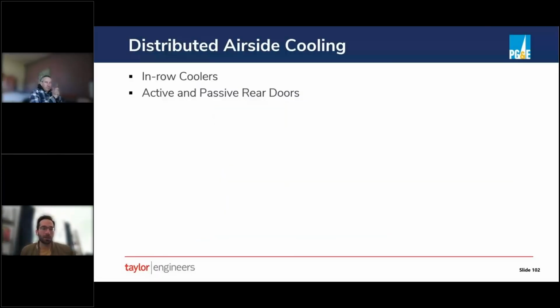Okay. Most of the systems that Jeff has been talking about use a flooded aisle design, where we essentially have very large air handling systems that then distribute air down cold aisle to multiple servers. There's another common strategy in data centers and in rack labs, which we'll call distributed airside cooling. And these often make sense in multi-level facilities or other locations where you just quite literally don't have either the roof space or the space on the side of the building to plug in a bunch of air handlers. And the two we'll touch on are in-row coolers, which Jeff already mentioned a little bit earlier, and then active and passive rear doors. In the past, we had a couple other options on these slides, but have since removed them since these are kind of the two dominant distributed strategies that you'll run into in data centers these days.